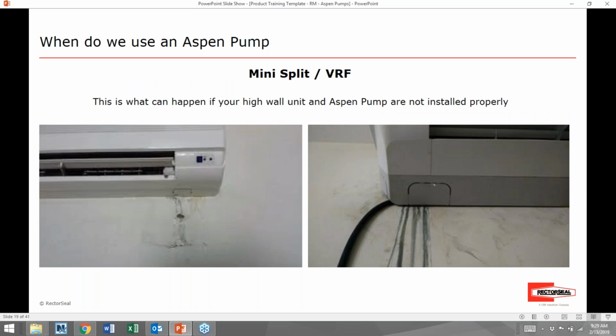When we don't install a mini split properly, we don't manage the condensate drain lines or Aspen pumps, this is what you can get. You can get leaks coming down the wall. These are two very, very minor examples of what can happen when you don't have that condensate management set up properly. I've seen many, many worse applications. So, underneath this high wall unit, there might be hardwood floors or antique furniture or expensive electronics. So it's very important to get this right.